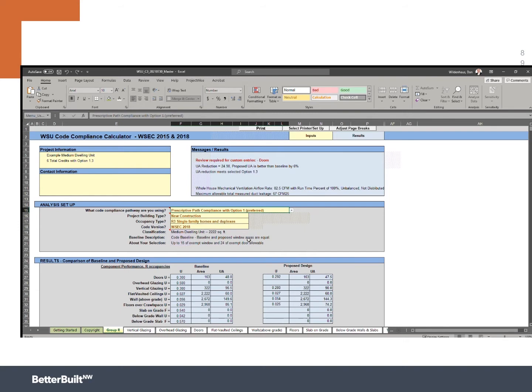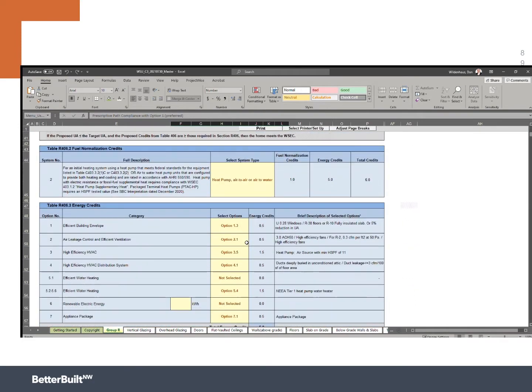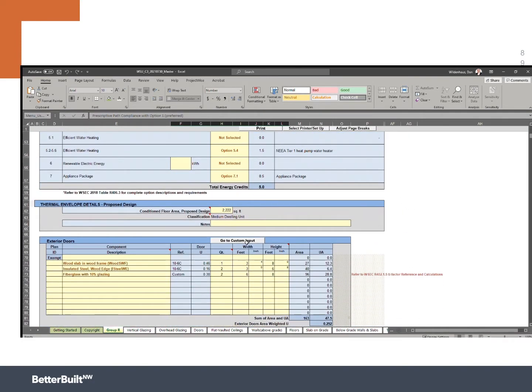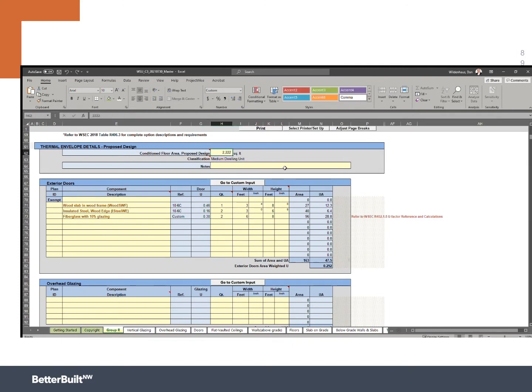So we put that, but I'm going to scroll real quick and show you where I can make that change if I wanted to. So right here under thermal envelope details and proposed design, I could alter this. It's very important to make sure you've got this right because the ventilation rate required by the energy code in the mechanical code is based both on the number of bedrooms you have and the square footage of the home. So it's really important that we get this right.